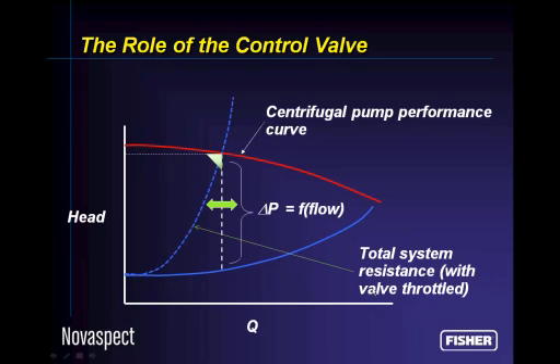When we have to throttle the valve to a more closed position in order to keep your process variable on set point, in essence, we're grabbing this blue curve here, which was the wide open control valve curve, and we were dragging it over until it's now in the position of the dotted line. You can see, where do we operate now flow-wise? We operate at the intersection of the new hydraulic balance curve and the pump performance curve at this point, and this is the flow rate we're delivering at that point.